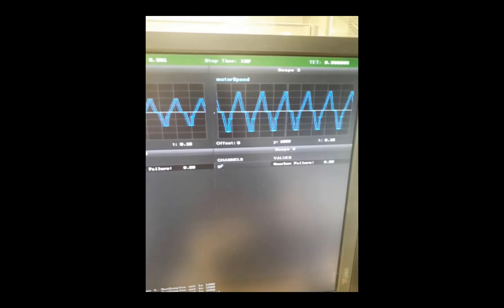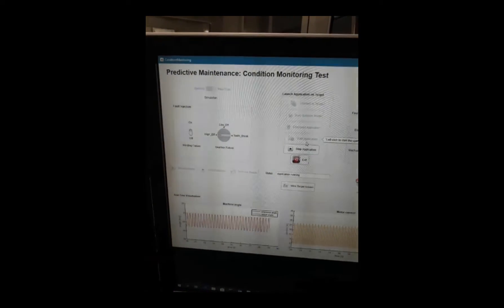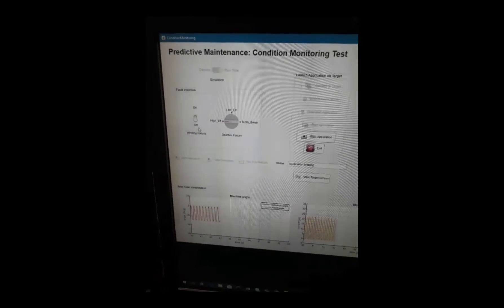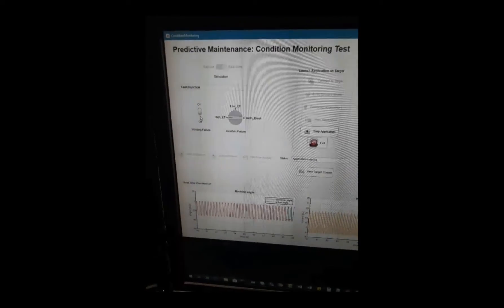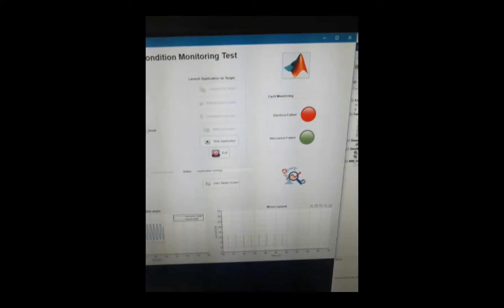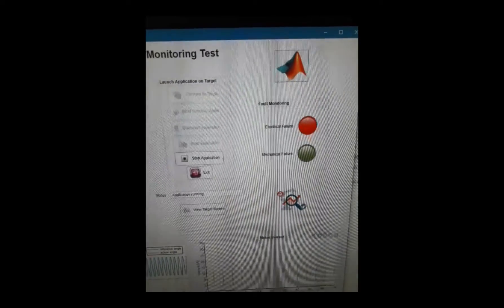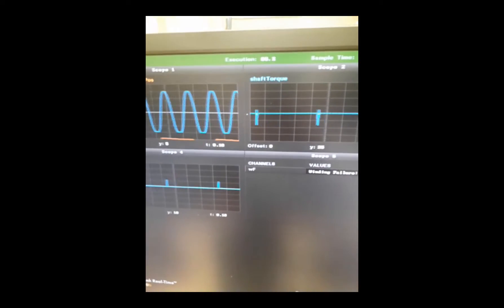We also have a couple of scalar values for failures on the mechanical side and the electrical side. From this app we can inject faults in the model. For instance, we can inject a fault on the electrical side and then immediately see how this impacts the behavior of the Flowpack machine. We can watch this in the GUI and see that we now have a red lamp for the electrical failure. This means the algorithm running on the PLC — deployed directly from Simulink — is behaving well and is capable of spotting a failure on the electrical side.